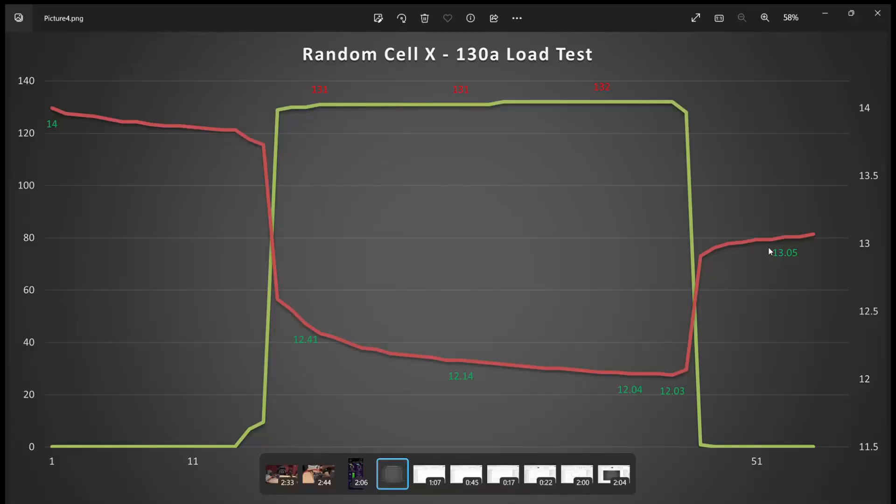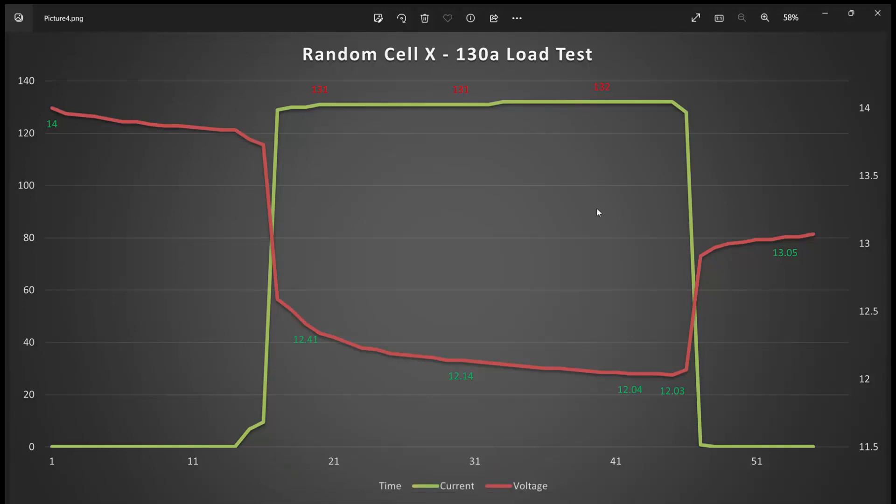And so finally, this is what we are left with. Once it's exported, you will see you just have the image of exactly the test. So you can see up here, it's around 14 volts. Once we turn on the 130 amp load, the voltage of the cell drops pretty quickly to about 12.4. Then 12.14, and by the end of the test, it's sitting right at about 12.03 when we turn it off, and where it quickly rebounds to 13. So you'll get used to how to read these pretty quickly if you've done a couple of these tests to know what you're looking for.